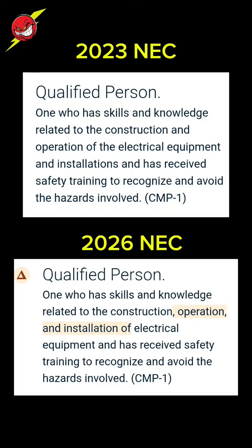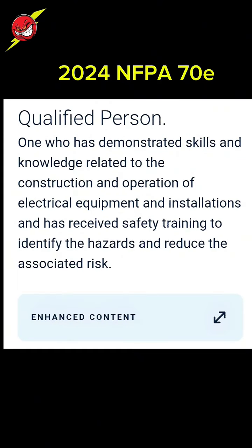You can see it's someone who has the skills and knowledge, so someone who's gone through training. But again, if we look at the definition from NFPA 70E, it's someone who's actually demonstrated those skills and knowledge. They also need to be able to identify the hazards and reduce the associated risk, not just avoid the risk like the other two definitions state.